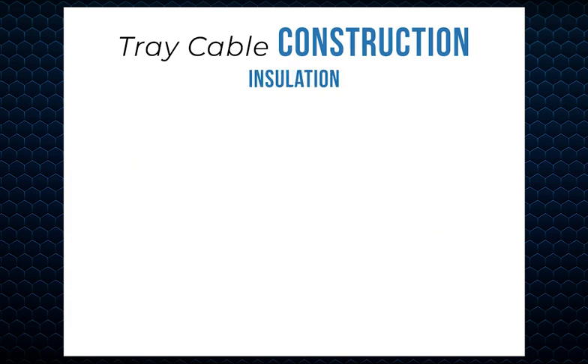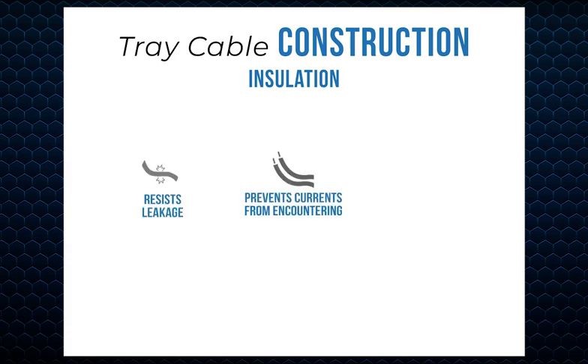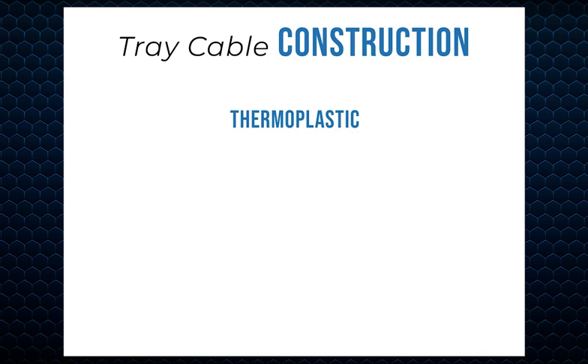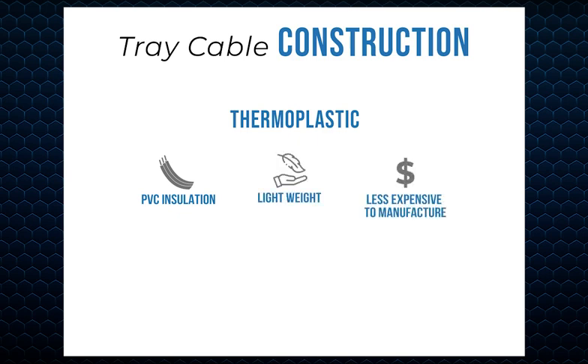Tray cable insulation keeps the conductors confined. Insulation resists electrical leakage, prevents the wire's current from encountering other conductors, and preserves the material integrity of the wire by protecting against environmental threats, such as water and heat. The safety and effectiveness of the wire depend on its insulation. Thermoplastic and thermoset are two common types of insulating compounds. THHN is a thermoplastic product. It uses a PVC insulation, which can lead to current leakage and dielectric breakdown in demanding circuits or from moisture or chemical exposure. It is lighter in weight and less expensive to manufacture.